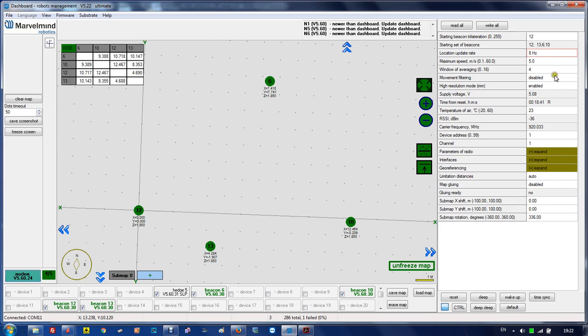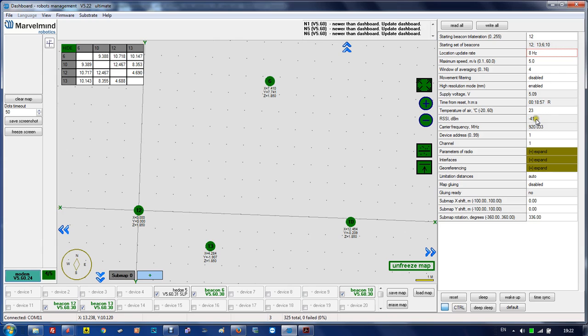It's for backward compatibility. We used to have resolution up to centimeters, now we have up to millimeters, and it's by default. Supply voltage shows supply voltage for the modem. This is time from reset. External temperature can be set, default is 23 degrees. RSSI is strength of radio signal in dBm.